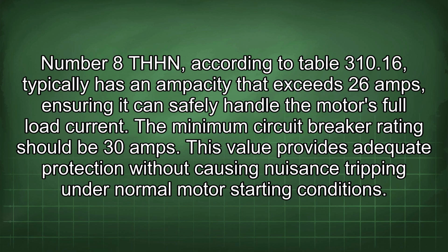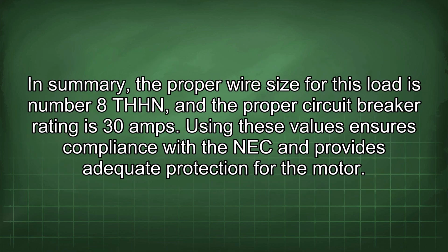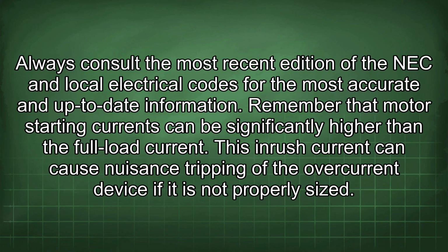The minimum circuit breaker rating should be 30 amps. This value provides adequate protection without causing nuisance tripping under normal motor starting conditions. In summary, the proper wire size for this load is number 8 THHN, and the proper circuit breaker rating is 30 amps. Using these values ensures compliance with the NEC and provides adequate protection for the motor. Always consult the most recent edition of the NEC and local electrical codes for the most accurate and up-to-date information.